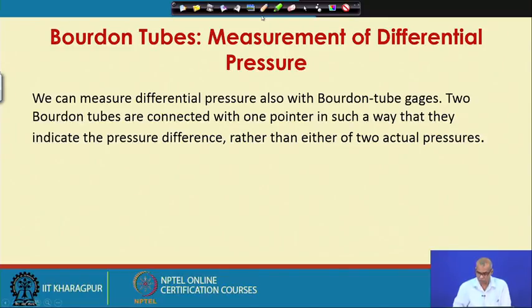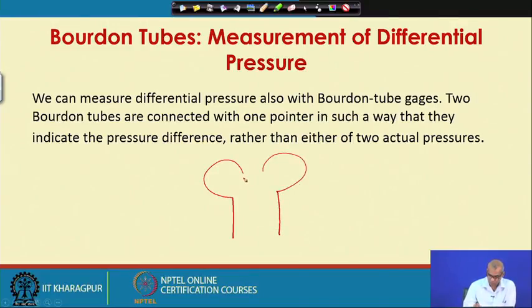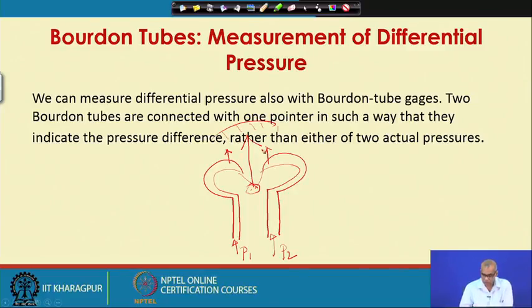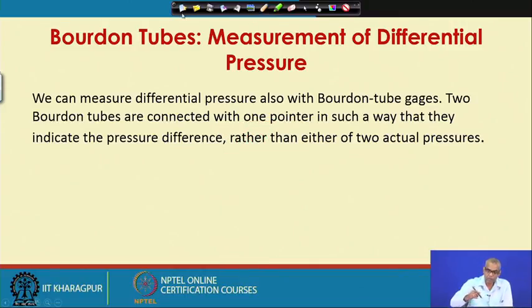Two Bourdon tubes are connected with one pointer in such a way that they indicate the pressure difference rather than either of the two actual pressures. So, what we do is as follows: you have one Bourdon tube and then you take another Bourdon tube. Now, these Bourdon tubes are connected by a single pointer. Now, we apply pressure P1 here, apply pressure P2 here. Now, this will try to displace in this direction, this will try to displace in this direction. So, the movement of the pointer will be a result of the difference between these two pressures. So, this way we can measure differential pressure using two Bourdon tubes.